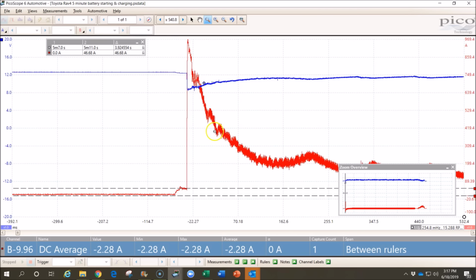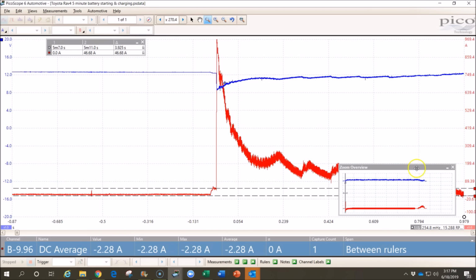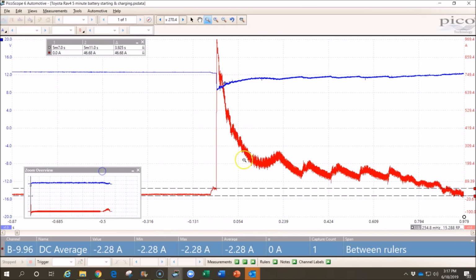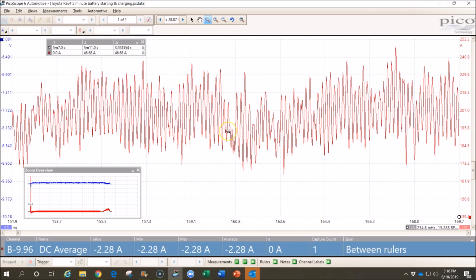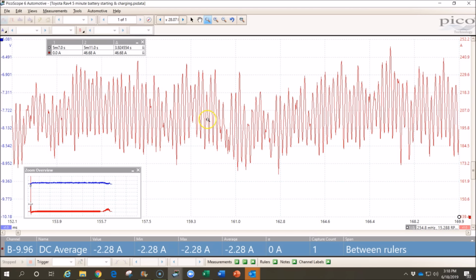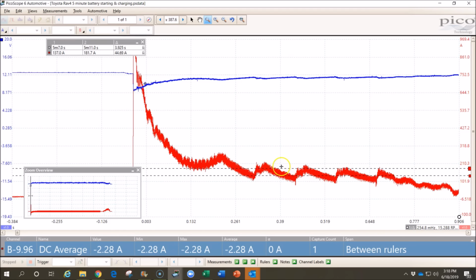The next thing we can look at, as we zoom out just a little bit here, is we see that these bumps represent the compression of the cylinders. But inside of here, these small bumps represent the brushes riding across the commutator segments, and they should look just like this. I do have enough to say that they're in good shape, because if I didn't, I would see them dropping out. You can measure the distance between the top and bottom of these hash marks, and it should be within about 50 amps of each other.